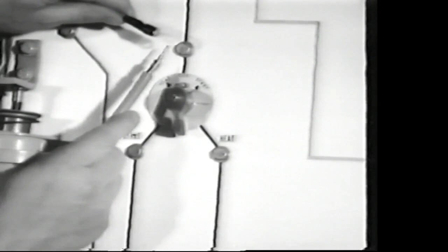This time we'll go directly to the problem. We check ahead of the heat start switch, and we have voltage. Now, we put the prod on the heat terminal and turn the switch to heat. There is no light, so voltage is not going through the switch. We know the switch is bad. A good switch would let voltage go to the relay. But we have no voltage here. We replace the heat start switch and test again.